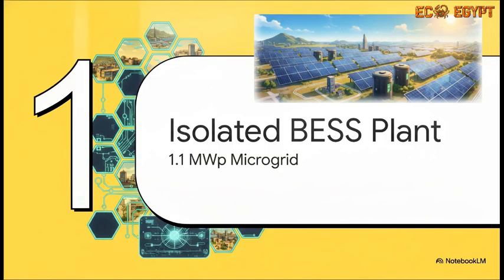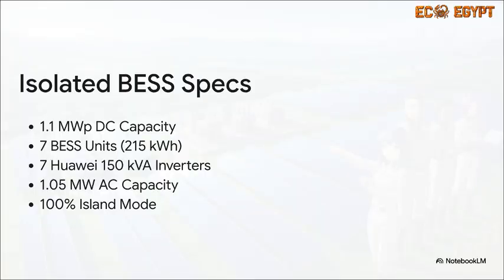The isolated BESS plant. Let's translate these massive specs into reality. Over on the DC side, we're looking at a formidable 1.1 megawatt peak capacity. Now, to manage storage for complete off-grid, island mode operation, this design relies on 7 distinct BESS units, battery energy storage, of course, with each one rated at 215 kilowatt-hours. To push that energy to AC, we're using 7 Huawei 150 kVA solar inverters. That brings our total AC capacity to a really robust 1.05 megawatts.